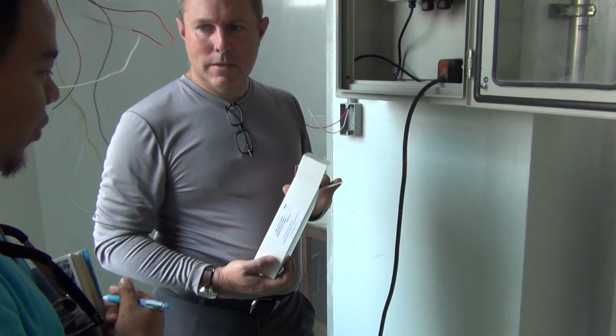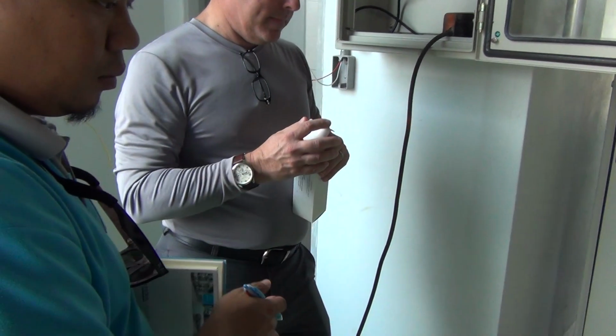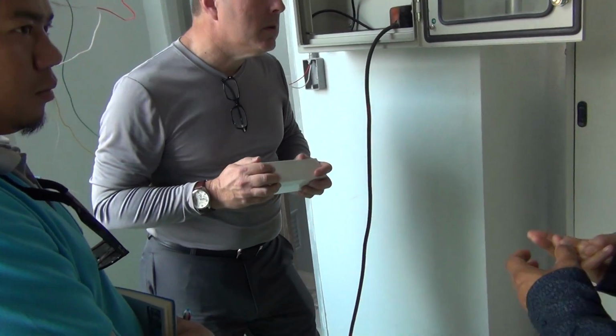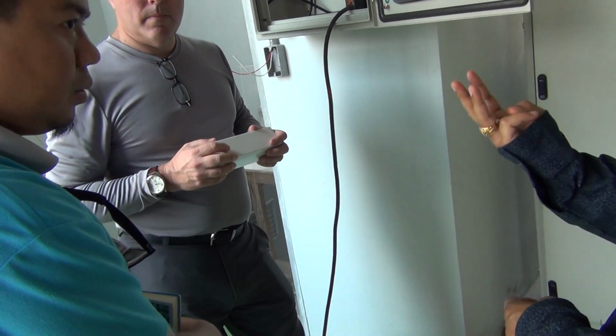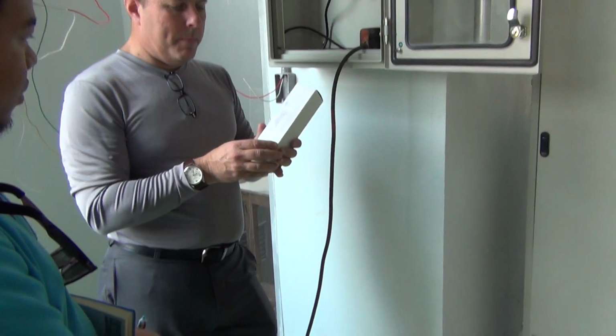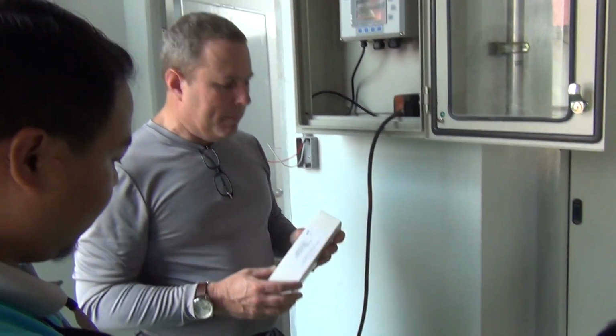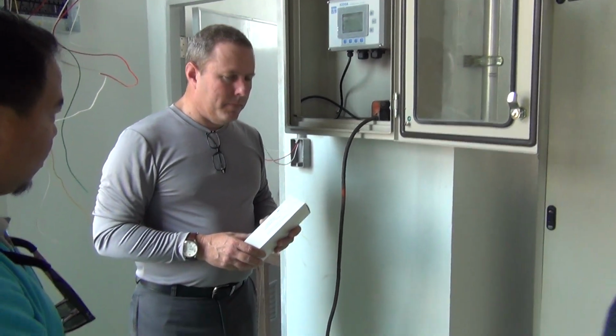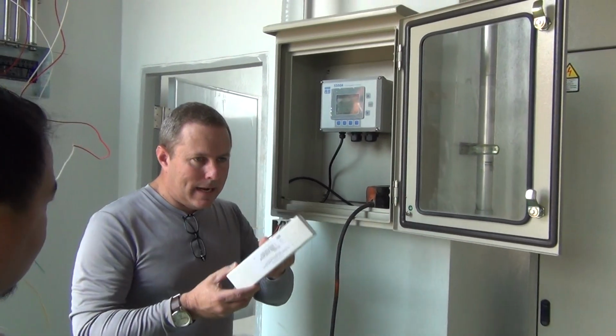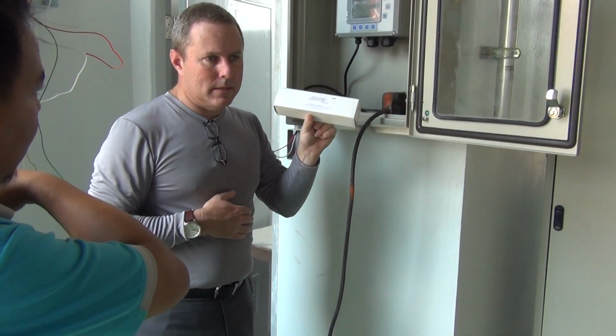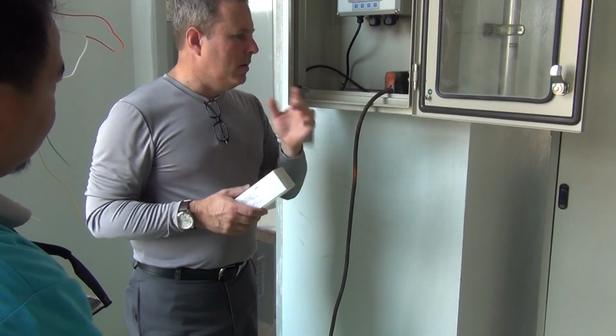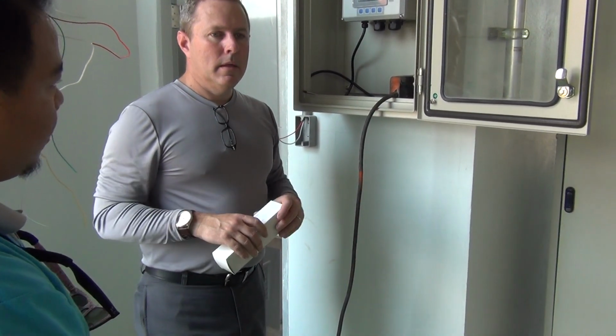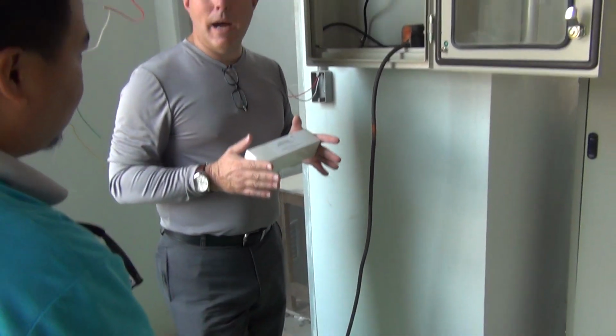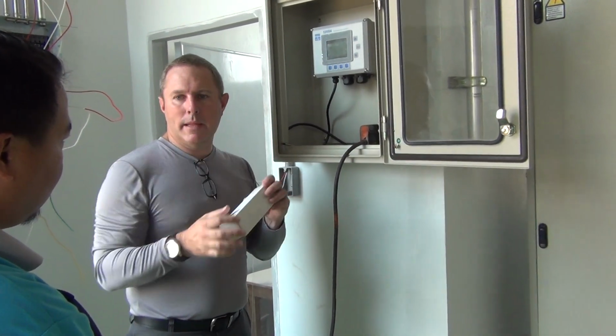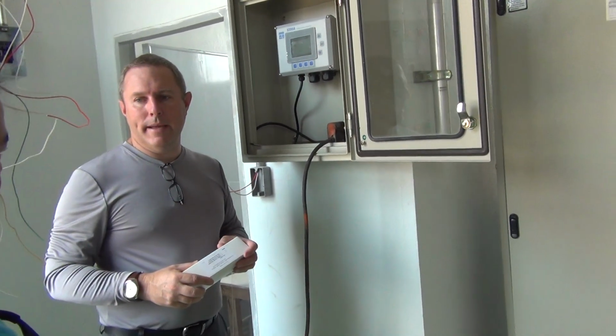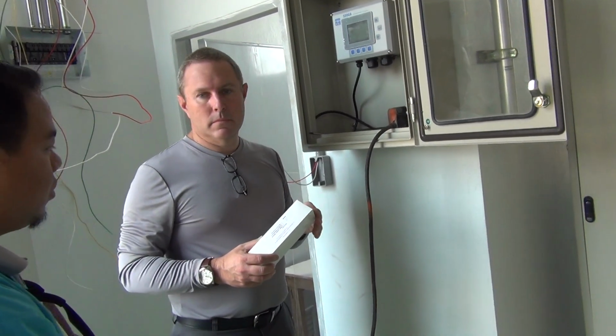Any questions? No question. There are 3 probes: pH/ORP, temperature conductivity, and dissolved oxygen. All the probes can be dry except this one. This is the only probe that has to stay wet. Temperature conductivity and DO, no problem, they can be dry. So, if pH is not a major concern, we can put a plug in the cable and you never have to worry about it. And we can disable it right here. It's up to you.